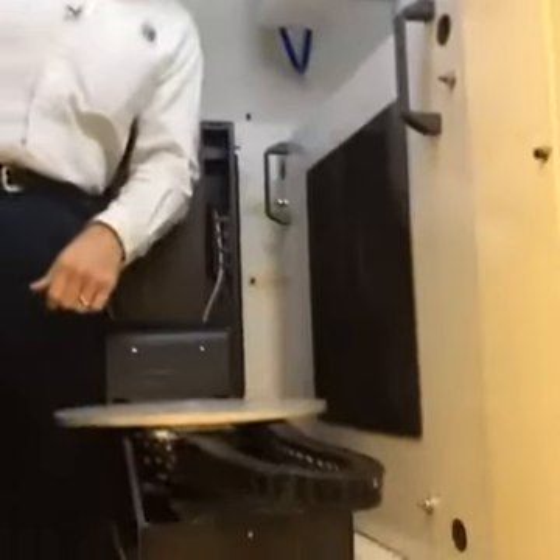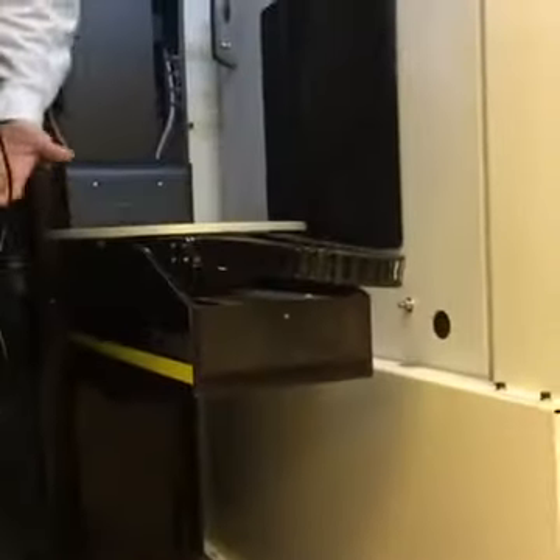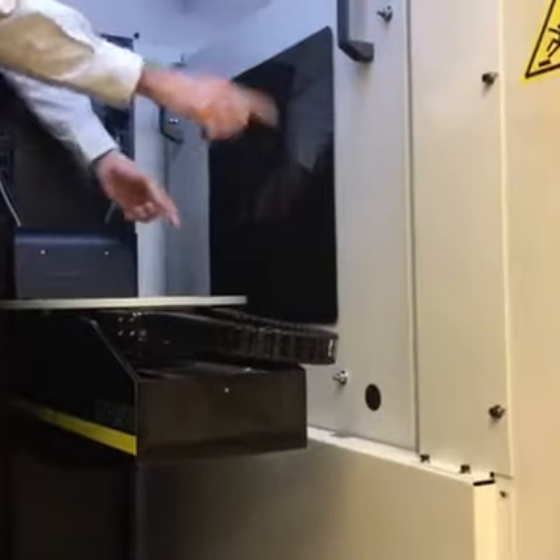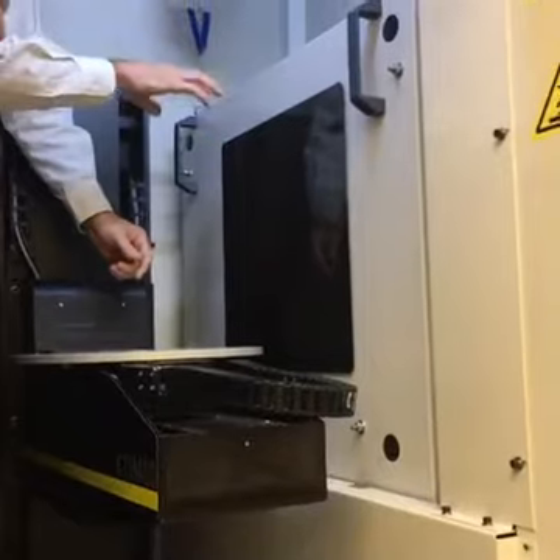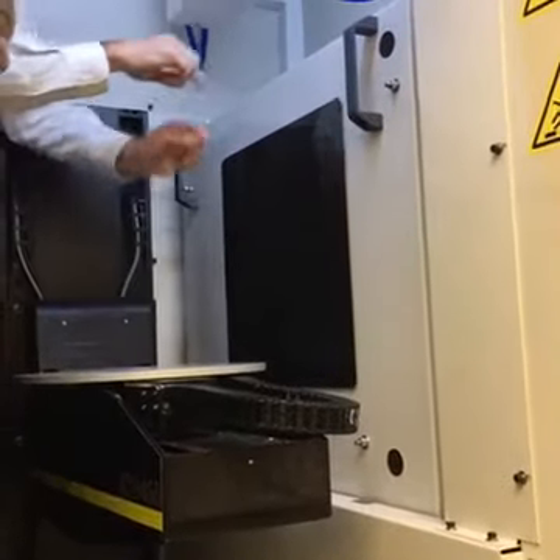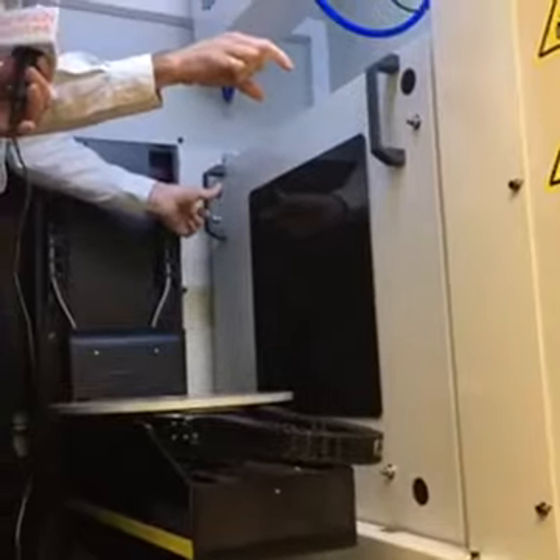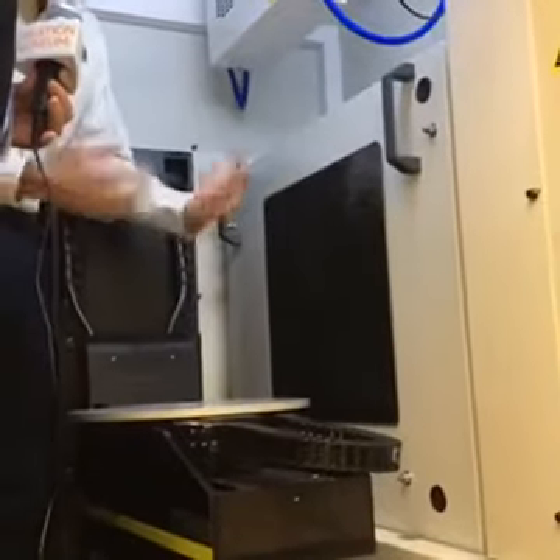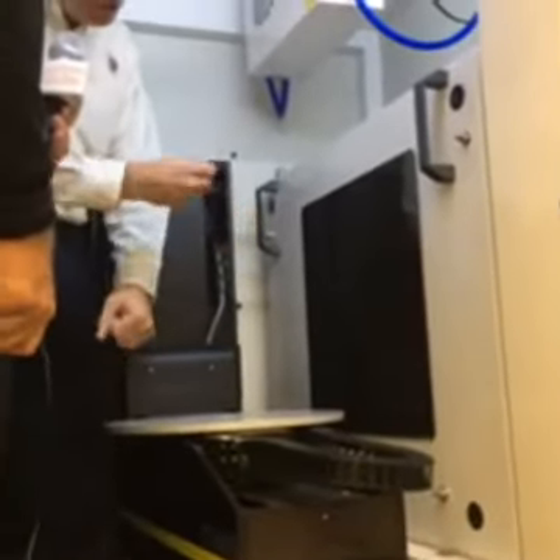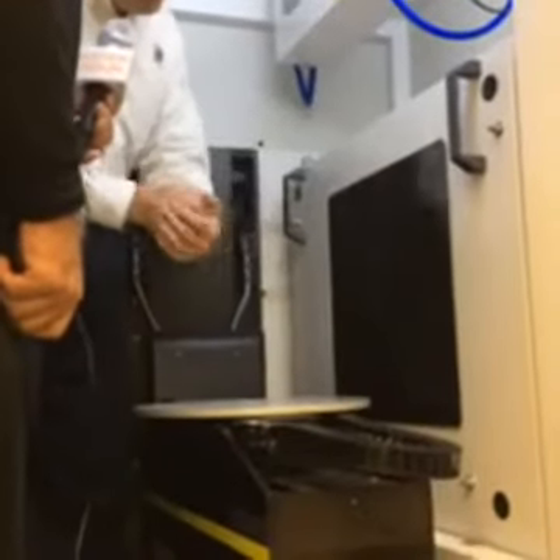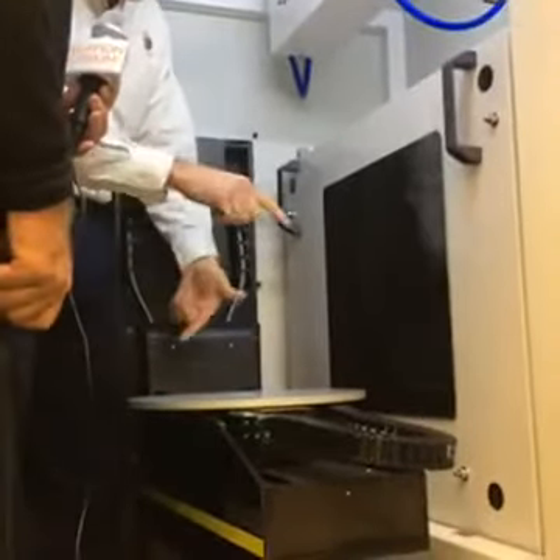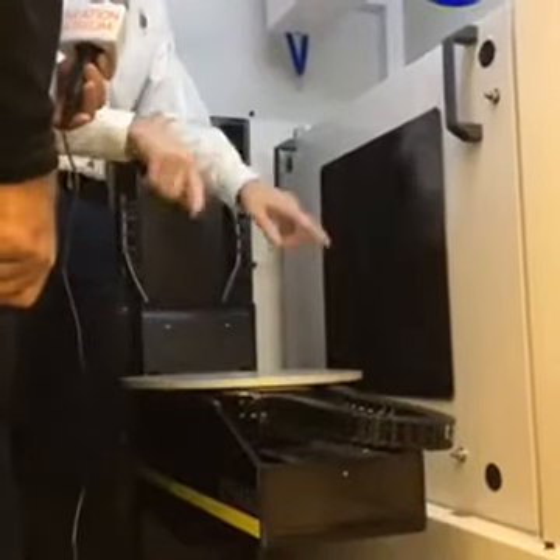No. Behind you is the X-ray source, and it's a 450 kilovolt source. The X-rays will come out of the center of this in a cone beam. Your parts will sit on this turntable, and the cone beam will go through the parts and hit a detector. We have two different types of detectors on this. We have a 16 by 16 inch Perkin-Elmer detector, and then a CLDA, curved linear diode array detector behind it. Each one could be used. And what happens is, as the cone goes through the material, only a certain amount of the X-rays make it to the panel, and then that makes an X-ray image. You slowly turn the rotating table, you take thousands of those images.